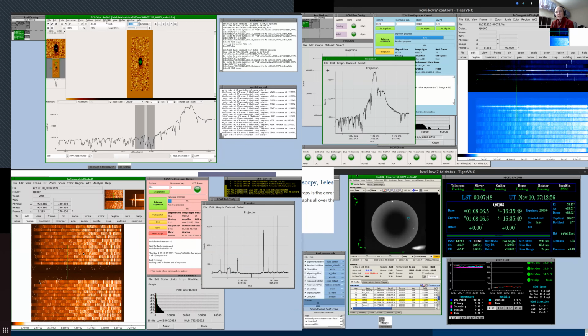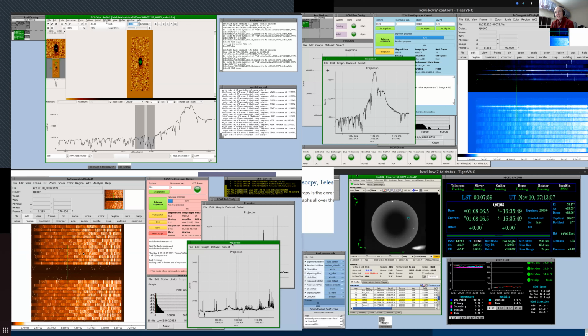There's a setting on the detectors called gain, which is the number of electrons that you get per photon. Right now, that gain is 5. So for every photon that's detected, we actually get 5 electrons coming out. But you can change that gain. KCWI has 2 settings, a gain of 5 or 10. A gain of 10 makes it a little bit more sensitive, but a gain of 5 allows you to expose longer without saturating the detector.